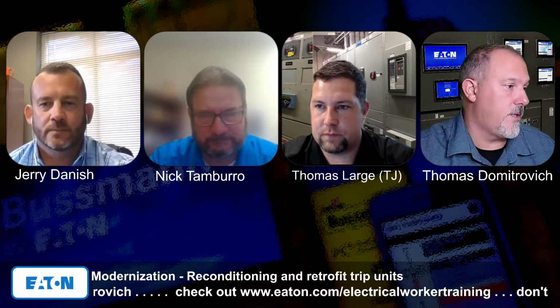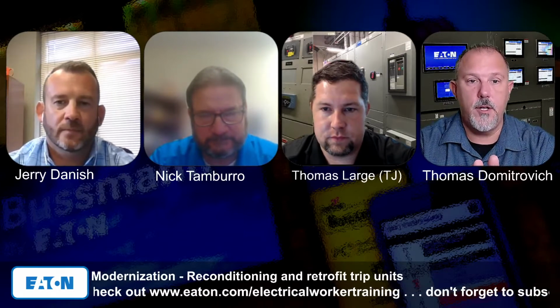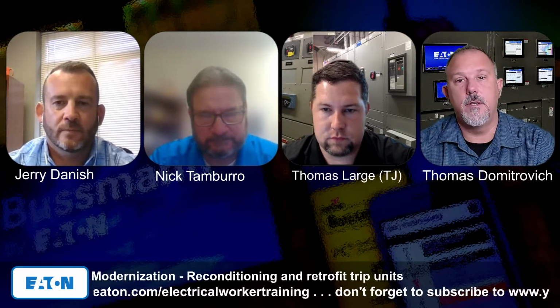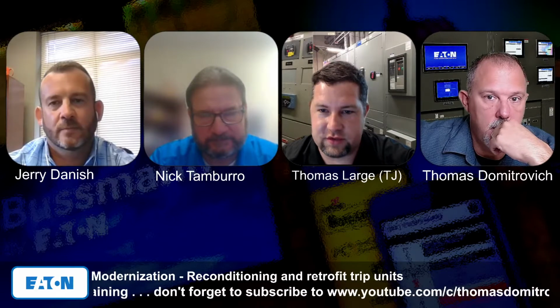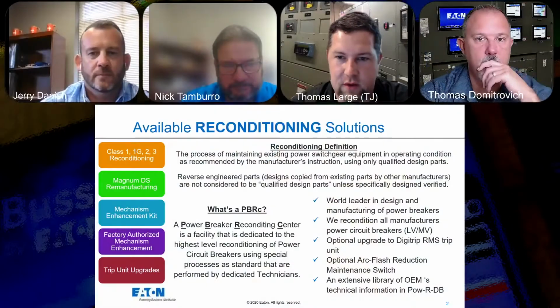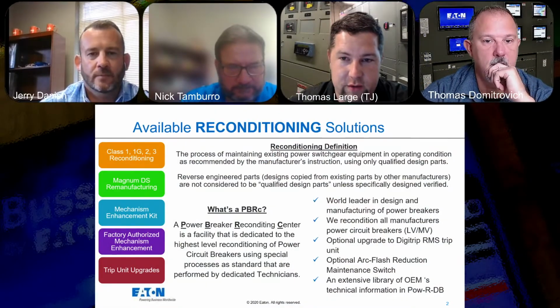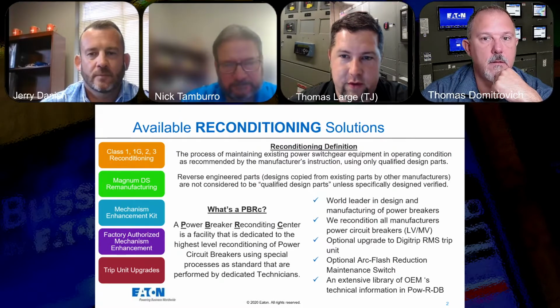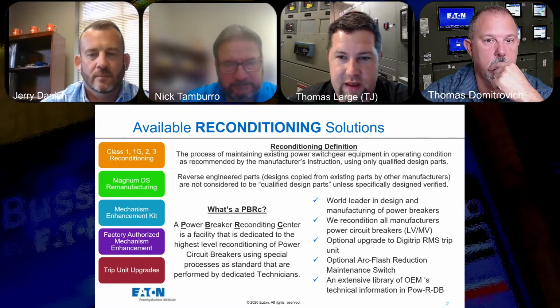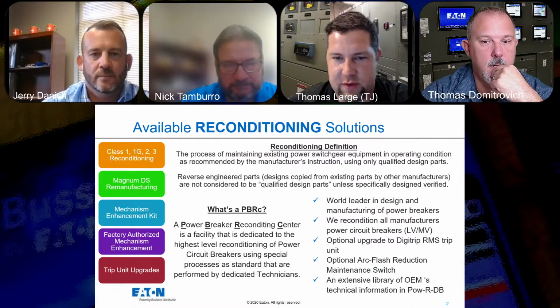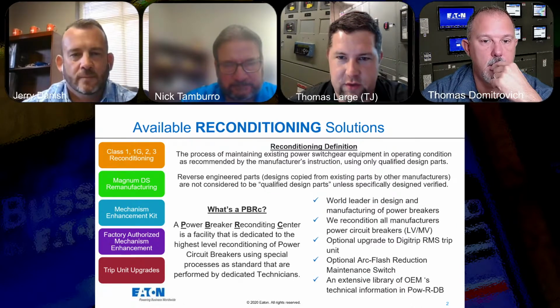So there's a difference between reconditioning and remanufacturing. The componentry is significantly different. A breaker from the 70s will mostly have steel components, aluminum components, and insulation product. A modern breaker, whether it's our Magnum, SPB, or even competitors' lines, has hard plastic or poly casings, not a traditional vintage power circuit breaker. So there's a bit of change when it comes to that.